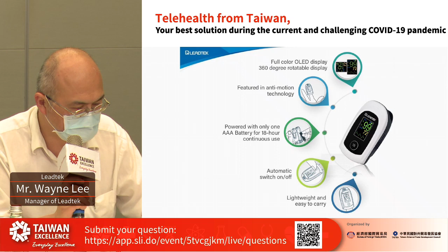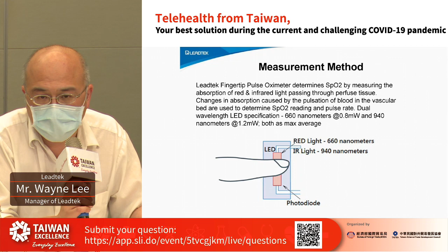Here let me introduce a little bit about the principle of the oximeter. An oximeter can take a reading of the blood oxygen in a non-invasive way. The principle is that it has a light source, and the light source emits light through the body part. On the other side of the body part, there is a photodiode. The photodiode takes the intensity of the light and finds the difference in light absorption between two different wavelengths. Normally we use red light and infrared light as the light source. For our device, we use 660 nanometers for red light and 940 nanometers for infrared light.